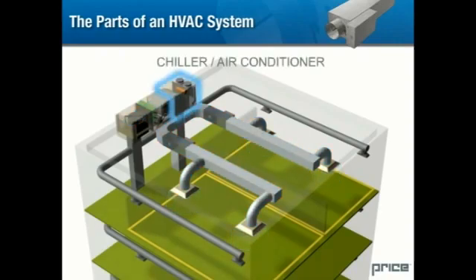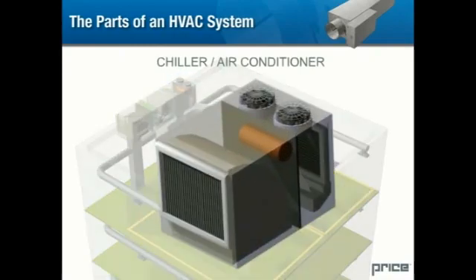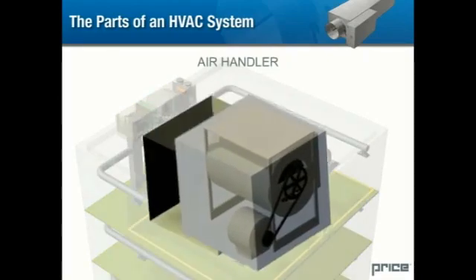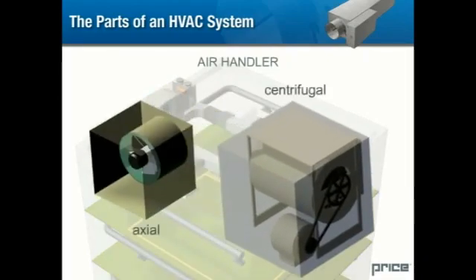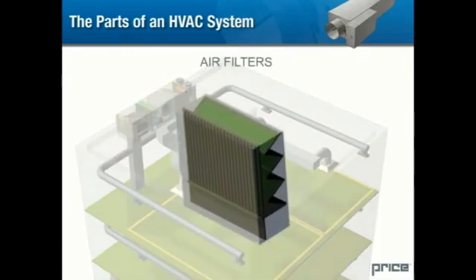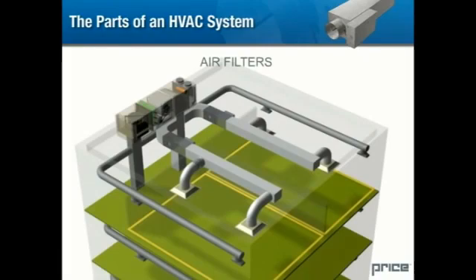The chiller or air conditioner utilizes heat exchangers and circulated fluid or gas to cool the air that is passed through it. The air handler is a fan or blower that moves air throughout the building's ductwork. Axial or centrifugal fan types may be found in the air handler. Depending on the requirements of the occupants and the activities in the building, various grades of air filters are used in the system. General purpose air filters will be included in the air handler itself, while more sophisticated filters, such as HEPA filters, may be used in the downstream ductwork.